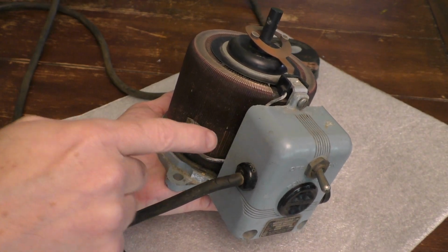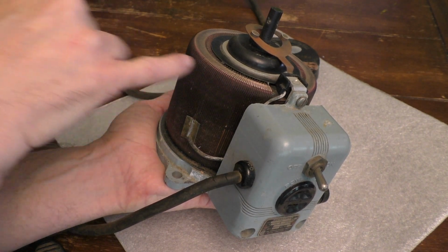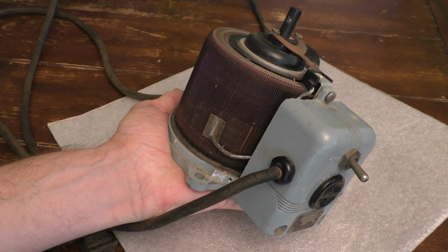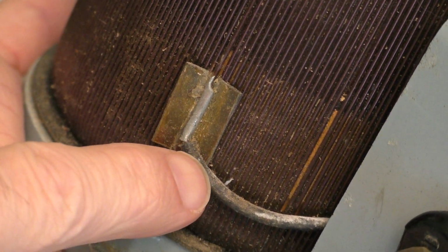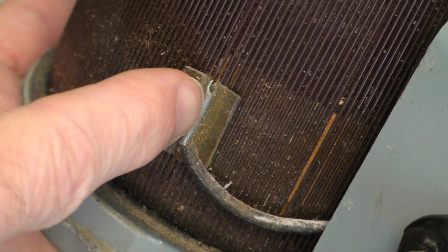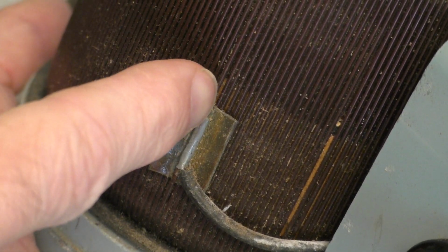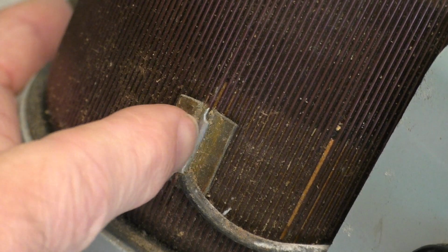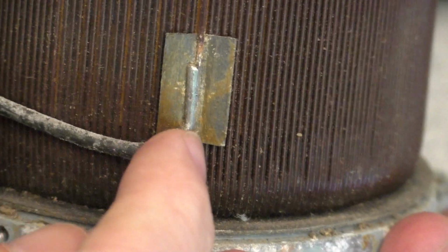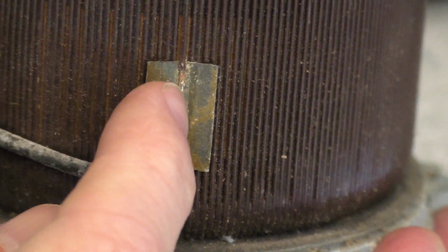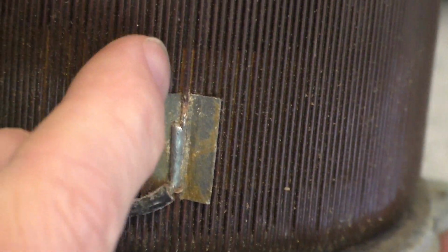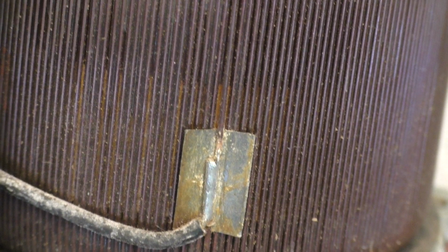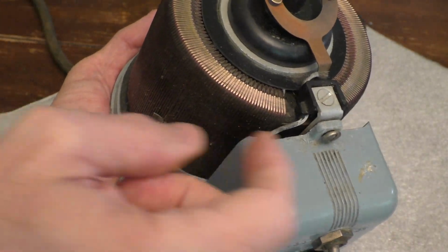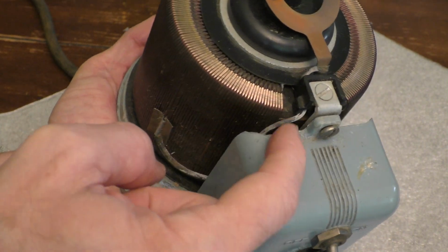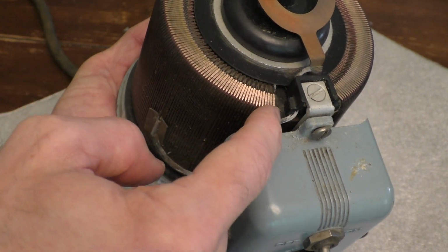Four of those five terminal connections are connected to your winding. You can see this little piece right there - this wire, I believe from terminal 5, connects directly into an exposed portion of the winding wire here. On the other side, I believe this is terminal 2, which is also connected to a different location in the winding. If I were to remove this little panel, you'd see a similar connection to the first winding of the coil.